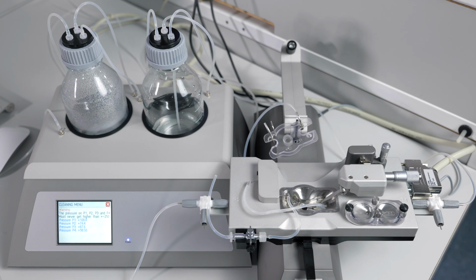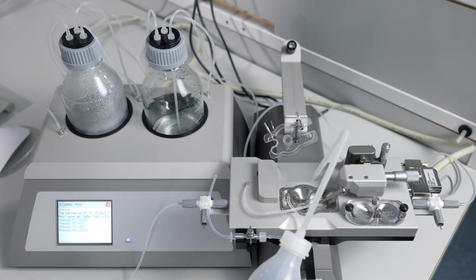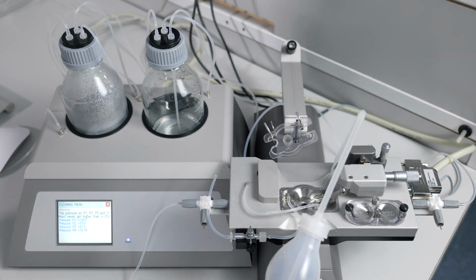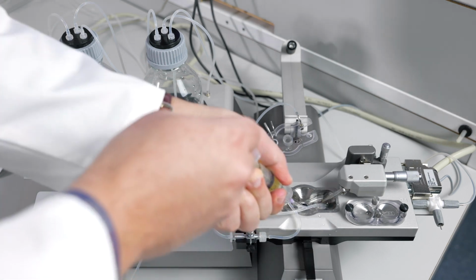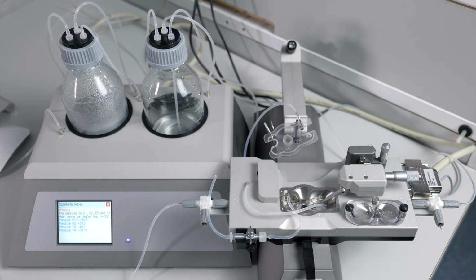It should also empty the pressure wells, but you can open the bleed valves in order to help facilitate air in these chambers. While the program is running with water and air, you should rinse the 112 pp chamber with distilled water 3 times. Add a small amount of water to the chamber, approximately 7 milliliters.